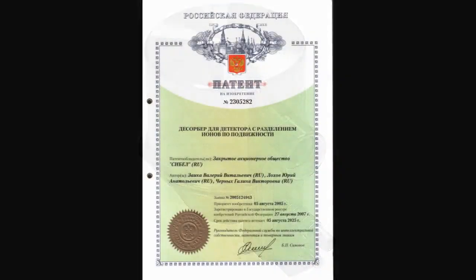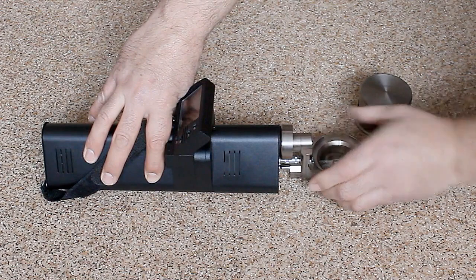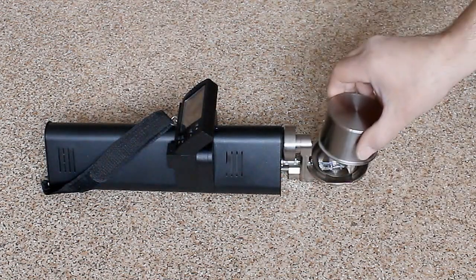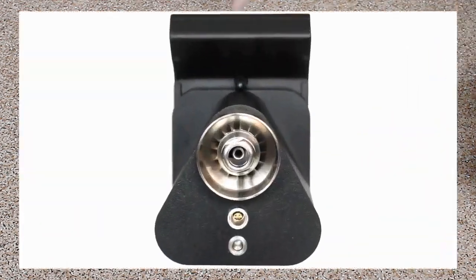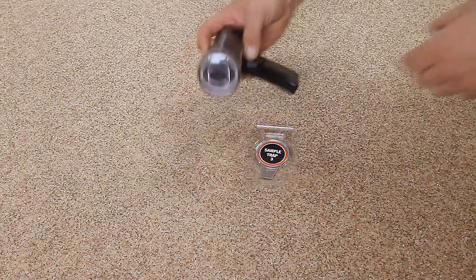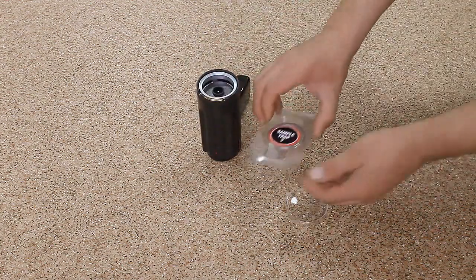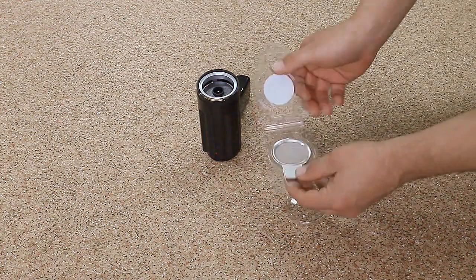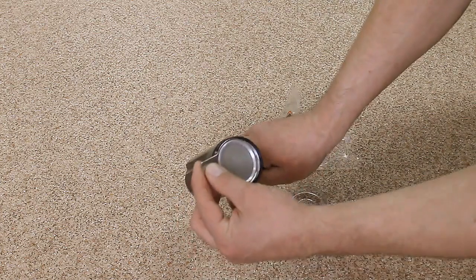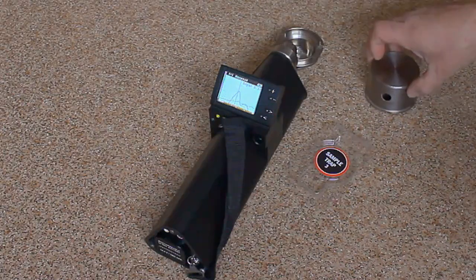The TWIN is a compact, reliable, and easy-to-use device. Sample heating and delivery to the detector is fully automatic and takes no more than 15 seconds. TWIN powering is provided by the ML2M detector via the socket at the front part of the detector. The sampling device is designed for collection of air samples by air absorption through a special metal trap. Powering of the sampling device is realized by an integrated nickel-metal hydride storage battery; the time of continuous operation with a fully charged battery is no less than 12 hours.